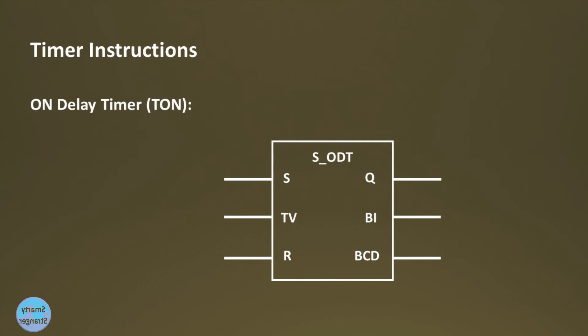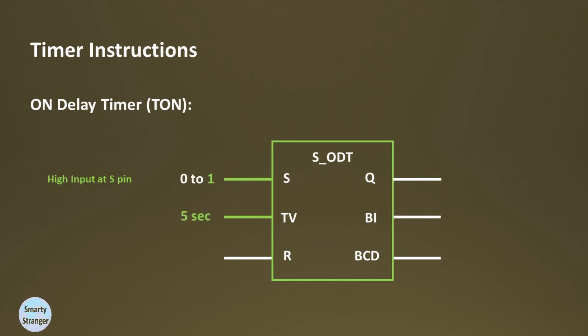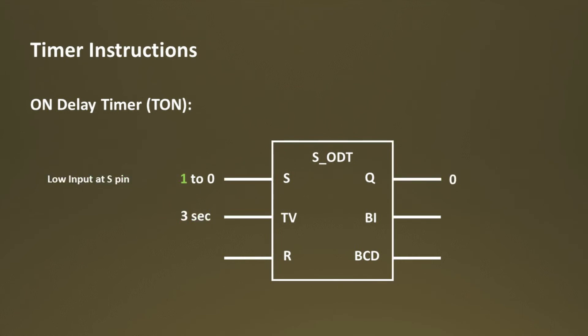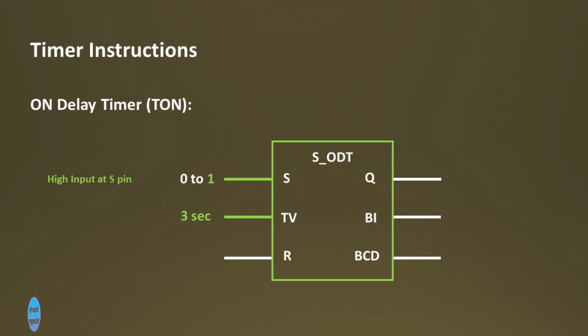Our next timer is the On Delay timer. When you need a delay in your logic operation — that is, the output should be energized after some time — you should use the On Delay timer. When S input detects a change from 0 to 1, the timer starts its timing and output Q waits for completion of the set time. When the set timing completes, the output is energized and remains energized until S pin changes from 1 to 0. If S changes from 1 to 0 before time elapses, the timer stops. If S changes again from 0 to 1, the timer restarts from the set value. If there is a high signal on R input while the timer is running, the timer and output stop immediately.